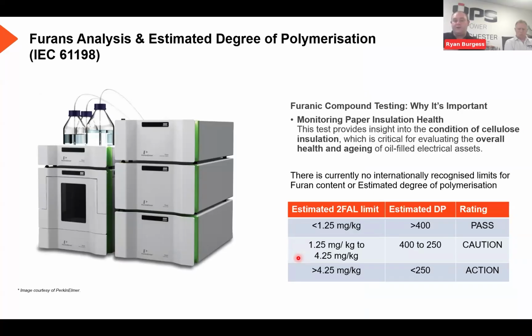So we'll look at the final test that we're going to talk about today, and that is furan analysis and estimated degree of polymerization. Over time, as the insulating material inside breaks down due to heat, moisture, and chemical reactions, basically the stuff we talked about earlier, furans, a compound known as furans, are released from the cellulose material, and we're able to detect the quantities of them to determine how the asset itself is aging over time. Because essentially the strength of the paper is the health of the transformer overall at a basic level.